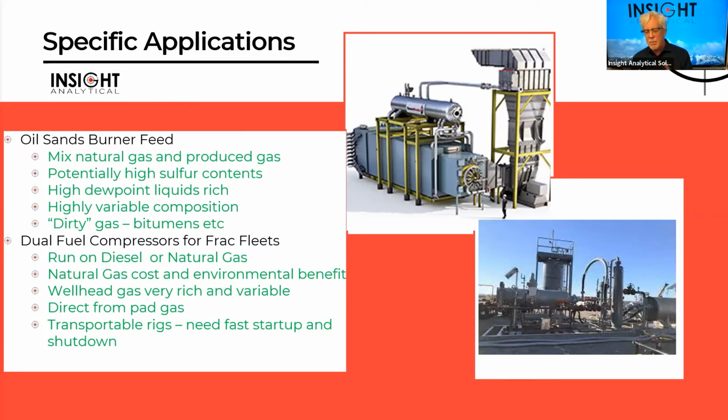That gas that comes back has been in contact with steam and with bitumen, and it can have a lot of small particulate that is sticky. It's bitumen-like, it's like tar. And so it creates havoc for a lot of analyzer sample systems. We produce this bitumen by making steam, so we run big boilers, steam generators, to help produce the bitumen.